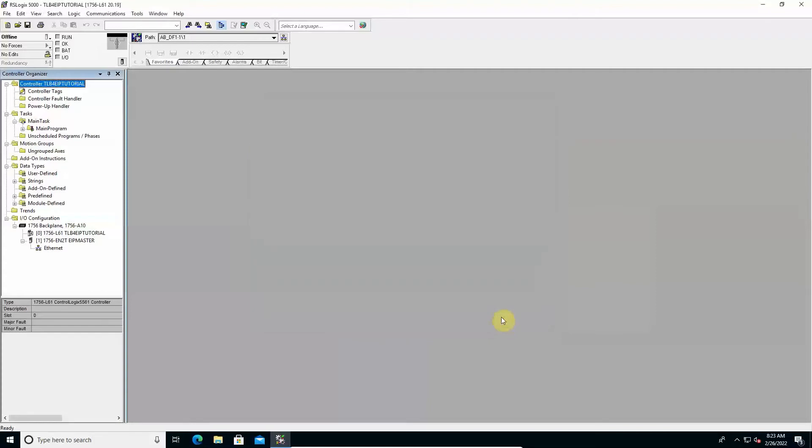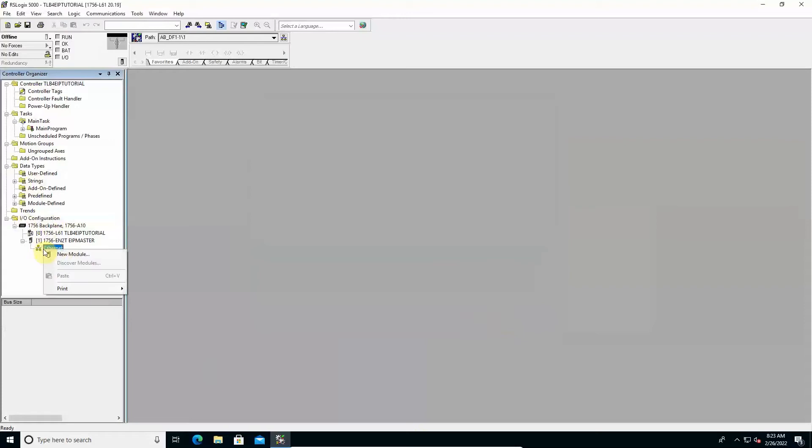To add the TLB4 to the project's Ethernet IP network, in the I/O configuration section, right-click on Ethernet IP network and select New Module. In the selection window that opens, type TLB4 to filter the available modules, select TLB4, and click Create.